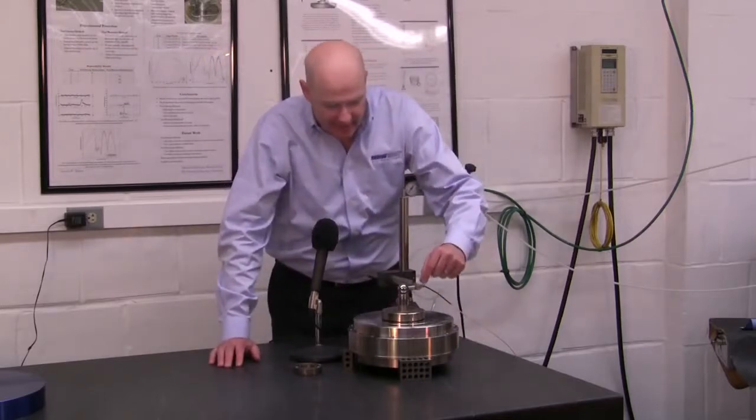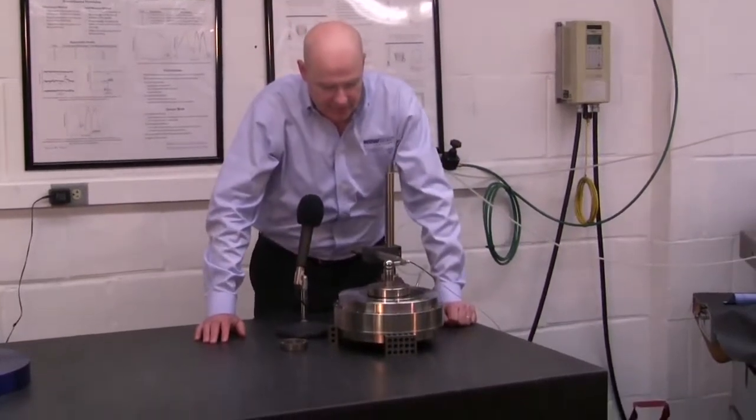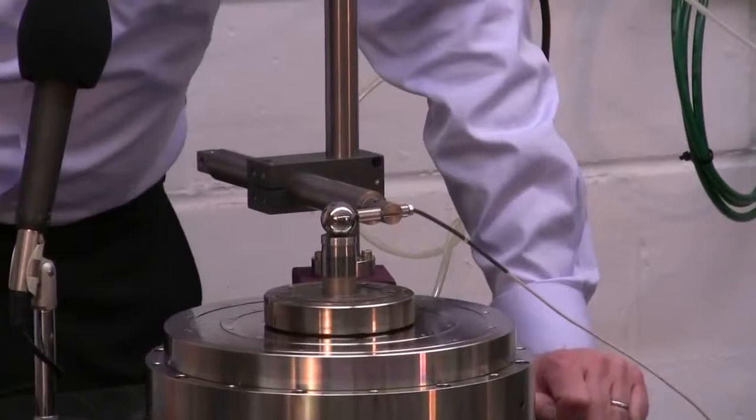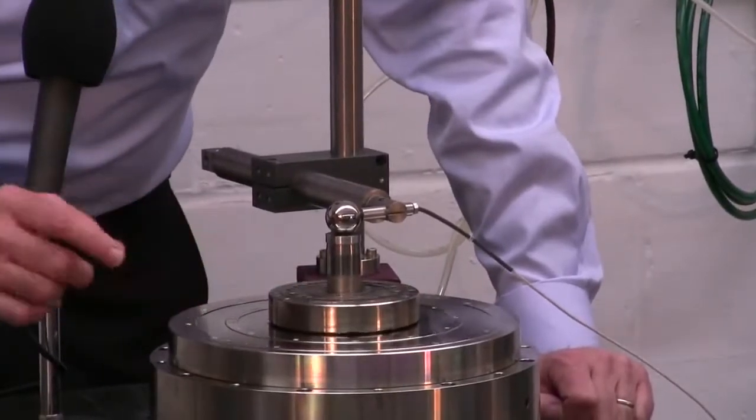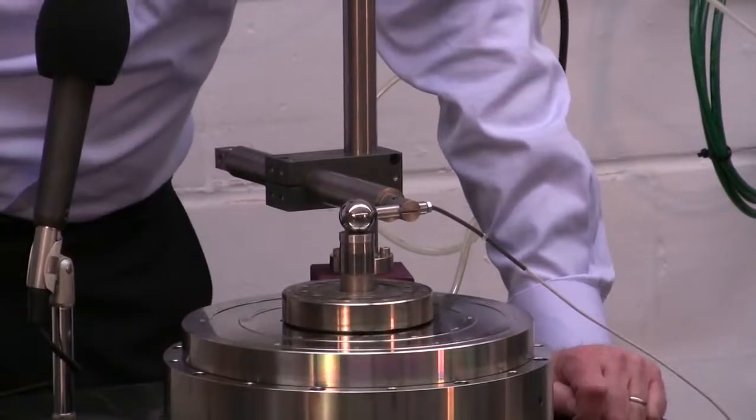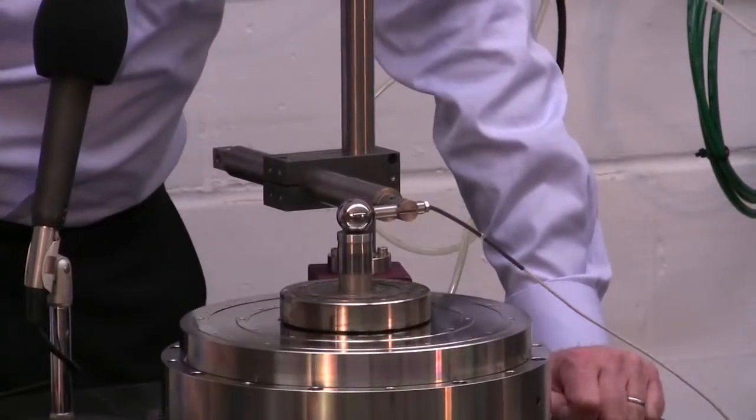We have a capacitance probe here that has nanometer resolution and a very accurate ball that's rounded to two millionths of an inch. It's attached to this test artifact which is centered to the axis of rotation, not perfectly, so there's some eccentricity that'll get taken out by the software.